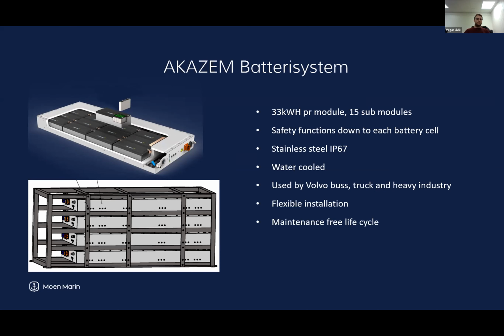The bottom pictures show a principle drawing of how we design our battery space. This battery module design allows for a very compact battery space, meeting all requirements from NMA and DNV, but it also gives greater safety. In case of an unwanted accident, like a thermal runaway, where gas and smoke come out of the battery module, there's less space to ventilate, so you get much faster ventilation of the battery space. This helps avoid gases and smoke filling the room and becoming a ticking bomb—you want that exhausted as quickly as possible.